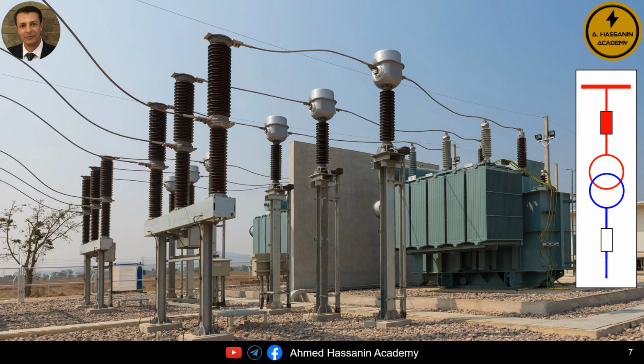Let us focus carefully on this point. The moment we connect the primary side of the transformer or apply voltage to the primary side, we will observe the occurrence of a very large current flowing inside the transformer. This current appears on the protection devices as if it were a short circuit current or an internal fault within the transformer. Unfortunately, the protection devices will immediately trip the transformer since they detect what seems to be a large short circuit or fault current inside the transformer, even though at this point the secondary side is still disconnected and there are no loads connected to it. Naturally, this large current is the magnetizing inrush current, which is essentially a no-load current, and its value can exceed more than 10 times the rated full load current of the transformer.